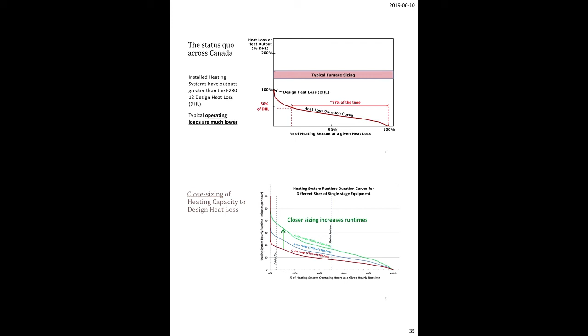But again, this is why we're starting to see it gets a little more complex. Low loads are weird, because you have to adjust to people's comfort and make sure it balances the home. So cooling loads, yesteryear, we used to require, cold air requires more CFM, right? 300 to 400 CFM per ton is about what we need on average. Every system's going to differ a little bit. And then you need about half of that for air that's hot, because cold air is cold and heavy, so it's more dense, right? So the cooling loads were smaller, heating loads were higher, but it meant that the ductwork leveled out at about the same size.